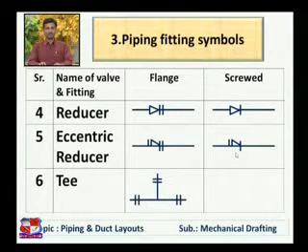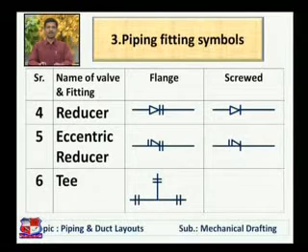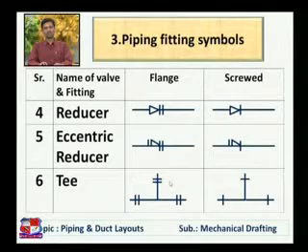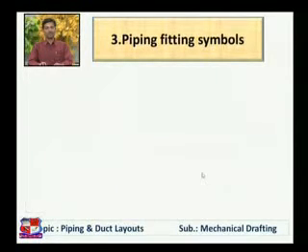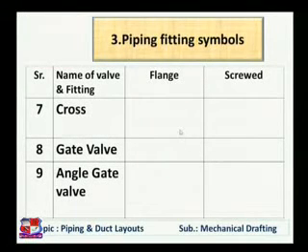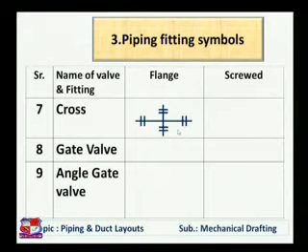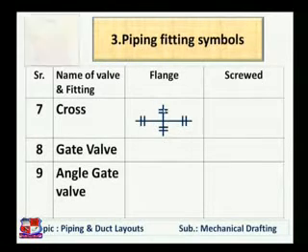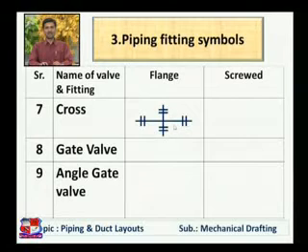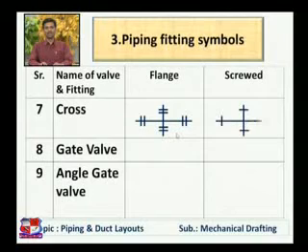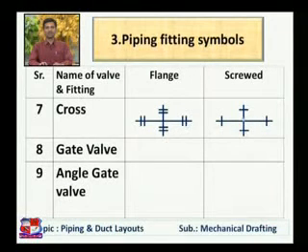To draw a Tee joint, its specific symbol is used. If it is a flanged Tee, two lines are drawn; if it is a screwed joint, one line is drawn at each end of the Tee symbol. Next is the cross — if two pipelines cross each other, they may be at a certain angle; in this case at a right angle. If joined with flanged coupling, two lines are drawn at each end; if screwed, one line is drawn at each end.